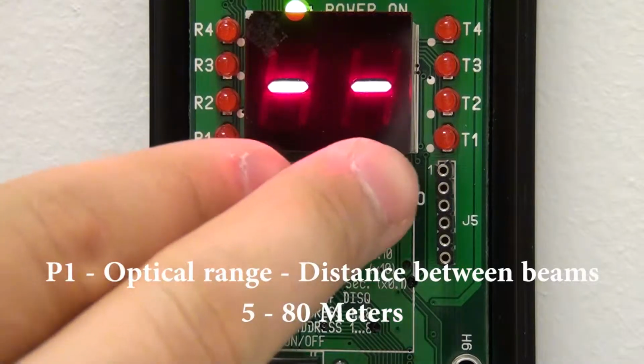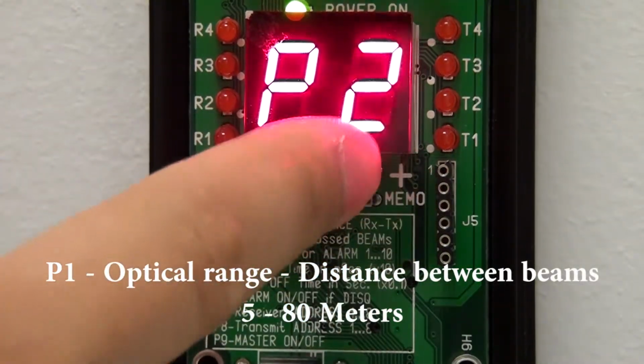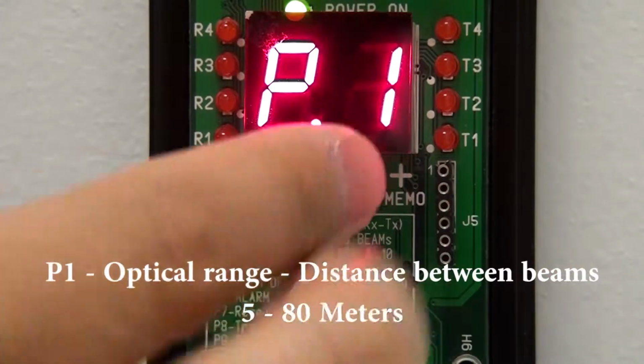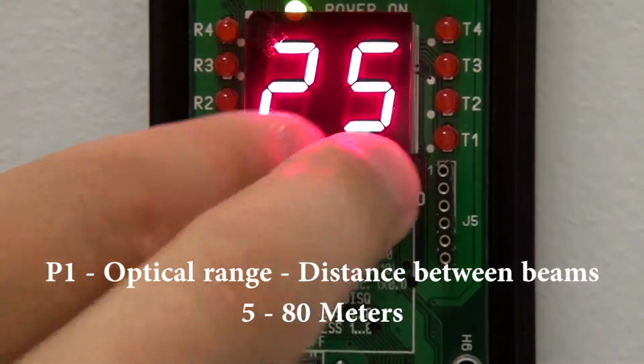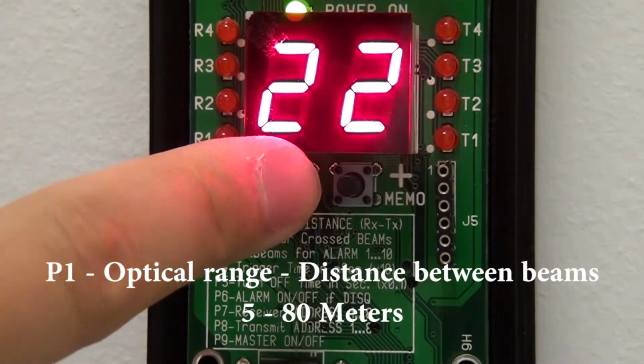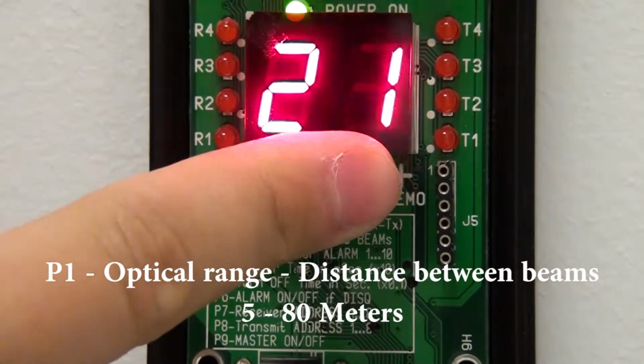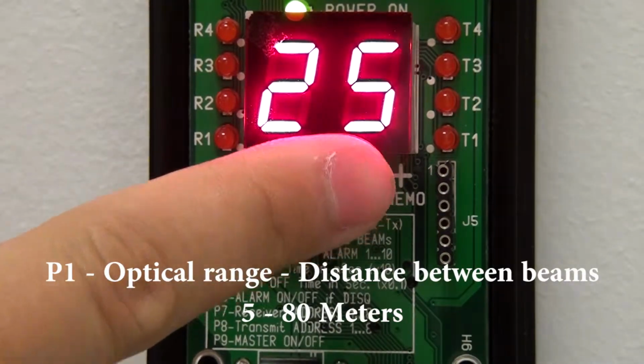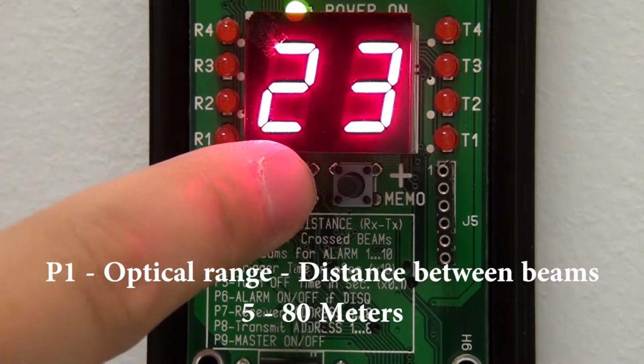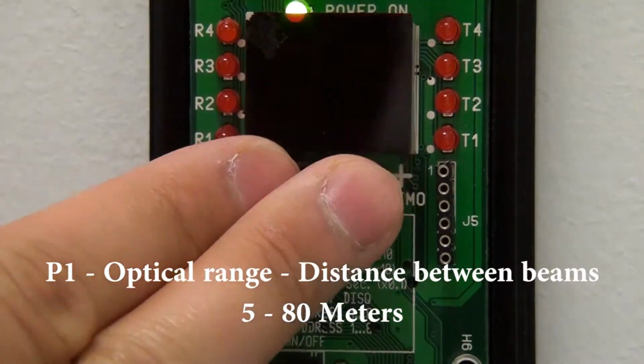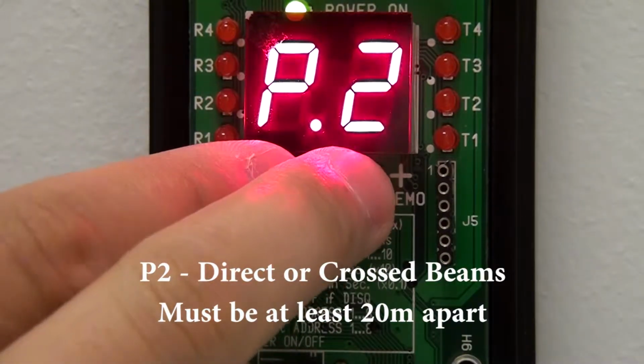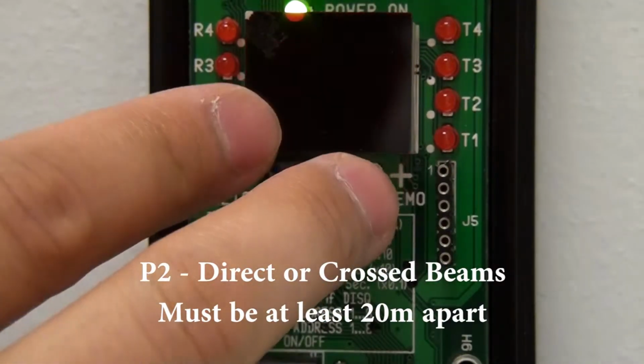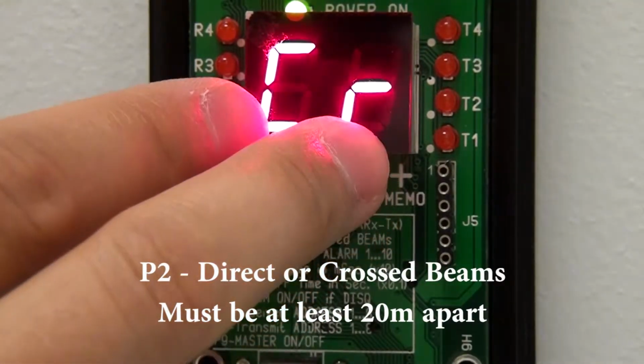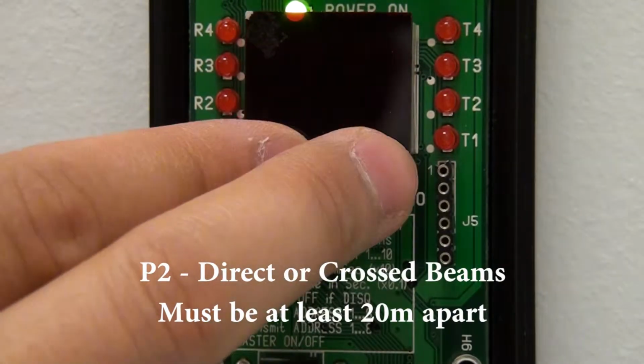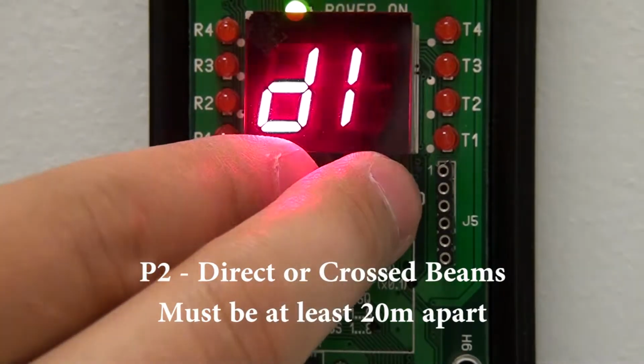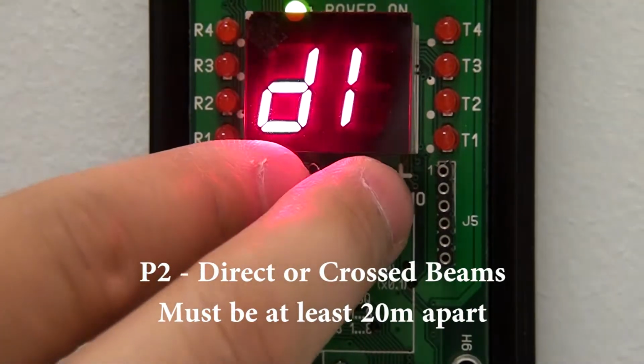We're going to talk about the different parameters here. We have P1 through P6. P1 stands for the optical range. So measure the distance between barrier 1 and barrier 2, and then enter the amount of distance in meters from 5 to 80. P2, we can use direct beams, or it can cross-link. If you want to cross-link your barriers, you'll have to be at least 20 meters apart or 65 feet.